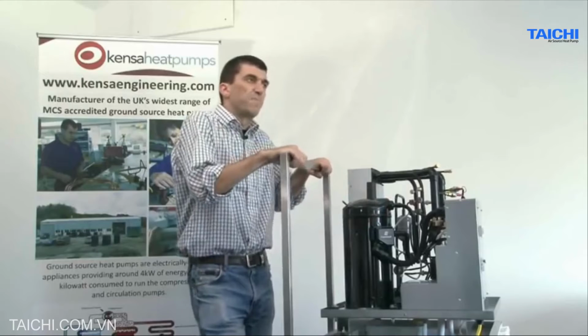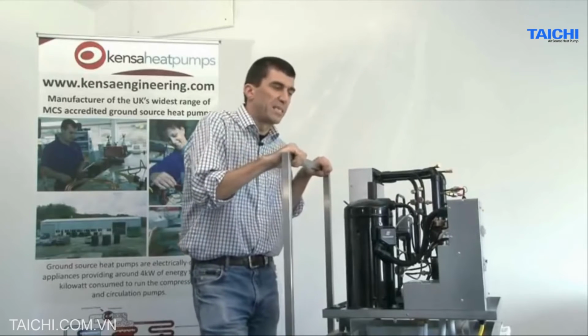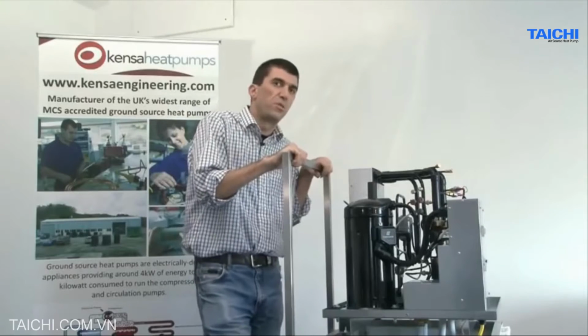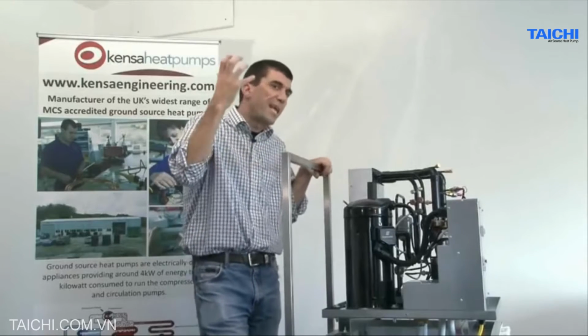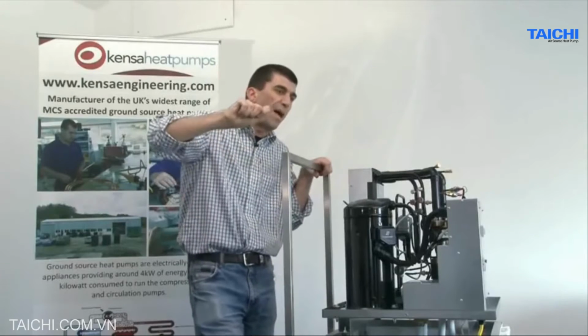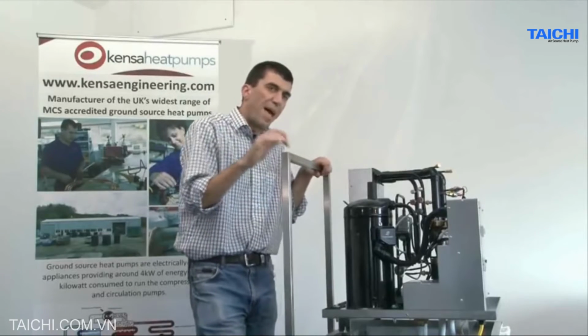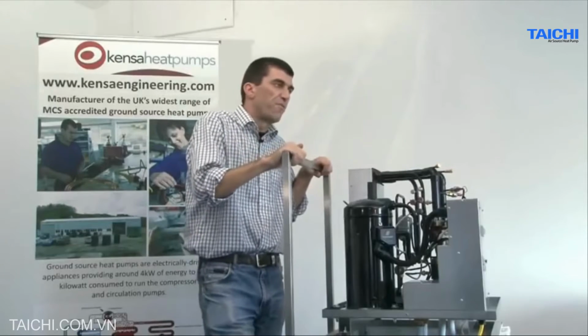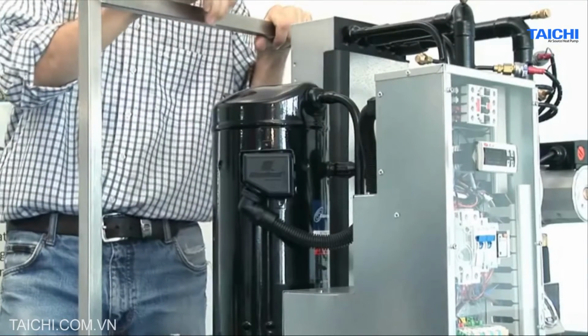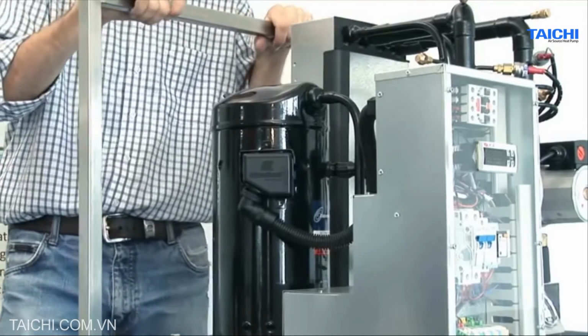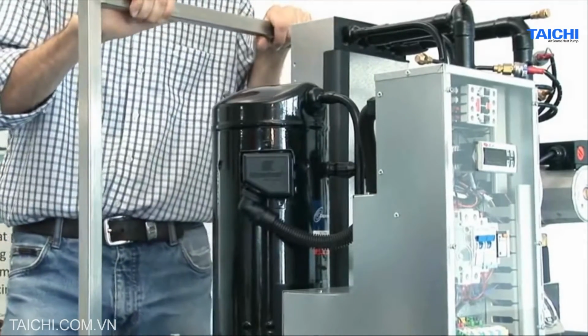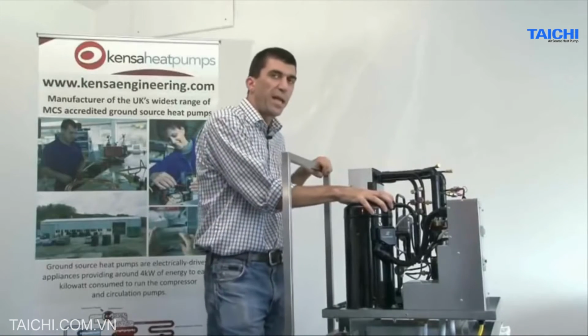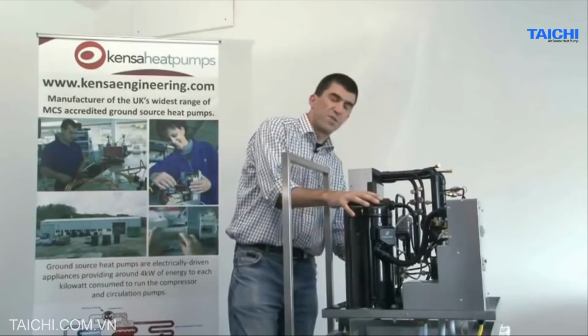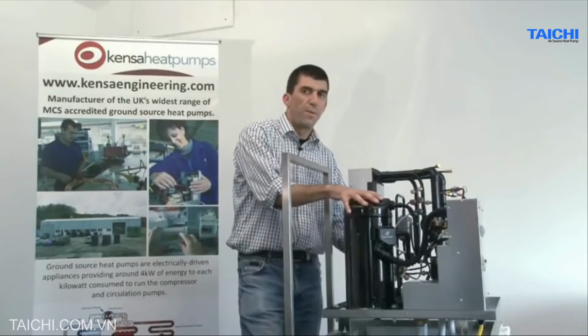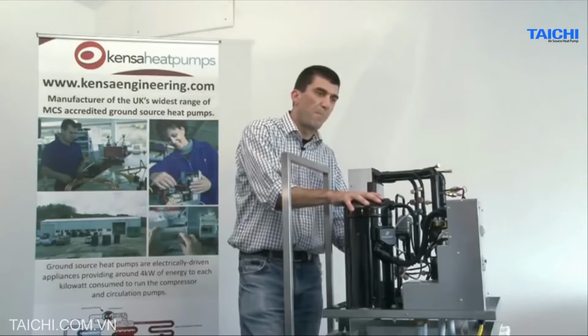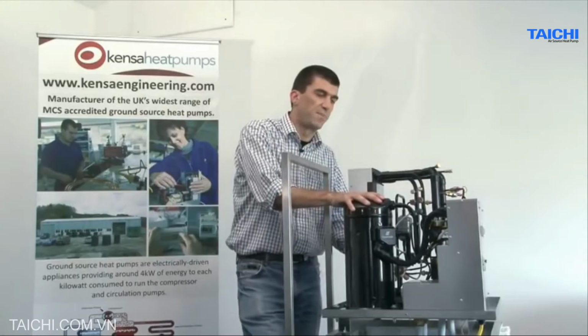The refrigerant is best likened to bottled gas. If you've got a bottle of gas that you use for a blowtorch or a stove, you'll know that when you shake the can you can hear there's liquid in it, but when you release the valve, vapor comes out. That's the magic, really, of a refrigerant gas. It has the same properties. It can be both a liquid or a vapor, and its state is controlled by its pressure. So by having a compressor working hard, fighting, if you like, the restriction of the expansion valve, we create 2 pressure states within the heat pump, a high pressure side and a low pressure side.